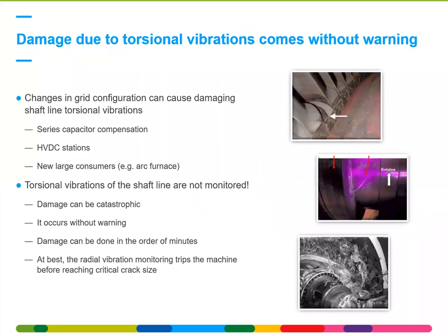And the issue with torsional vibrations is that damage actually comes without warning. You could have certain changes in grid configuration, which can cause damaging shaft line torsional vibrations. Examples which will be further detailed are when you have series capacitor compensation on the grid, HVDC stations, or new large consumers, for instance, arc furnaces. Those major components are known to have potential interaction between the grid and the power plant. And the issue with torsional vibrations is that these are not monitored by default.